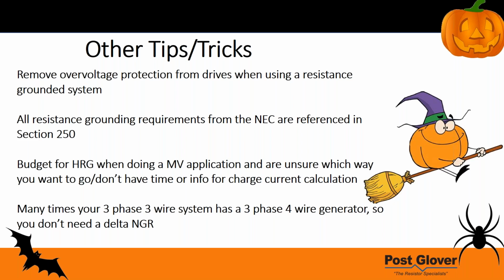So when we're talking about medium voltage applications, this is the kind of thing I mentioned before. A lot of times I get medium voltage applications where they want to use high resistance ground, and they're like, okay, this is what I want to do. I'm like, okay, do you want to do a charge current analysis to make sure you can? And they're like, we don't have enough information at this point. So at that point, if you have the ability to conservatively estimate those values, then go for it. If you don't, then I would just budget for the more expensive application, which would be the HRG, and then you can do either one after you get your calculation done.